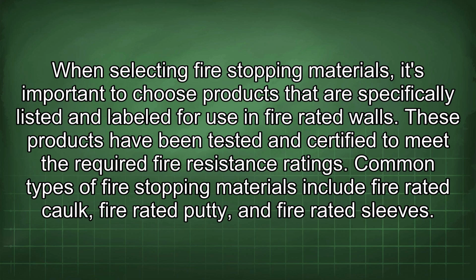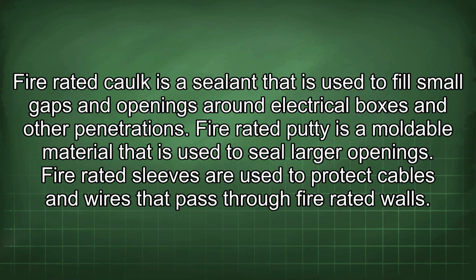Common types of fire-stopping materials include fire-rated caulk, fire-rated putty, and fire-rated sleeves. Fire-rated caulk is a sealant that is used to fill small gaps and openings around electrical boxes and other penetrations. Fire-rated putty is a moldable material that is used to seal larger openings. Fire-rated sleeves are used to protect cables and wires that pass through fire-rated walls.